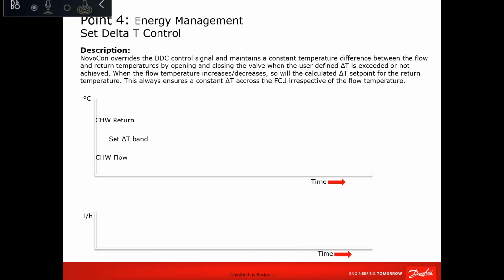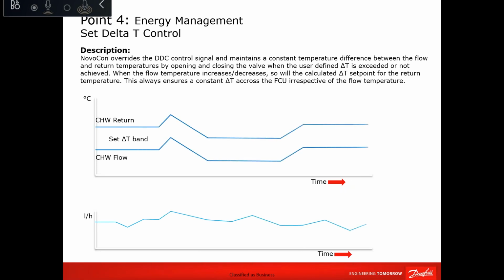Then you will see oscillations in the delta T, ups and downs, but the average delta T will be there. When you make set delta T control, it will respond to only the delta T variable. So Novocon will not accept the DDC flow control and will only maintain constant delta T. This is useful when you are putting a Novocon on a branch and you need the predefined delta T, and that's it. So this can be used as well.